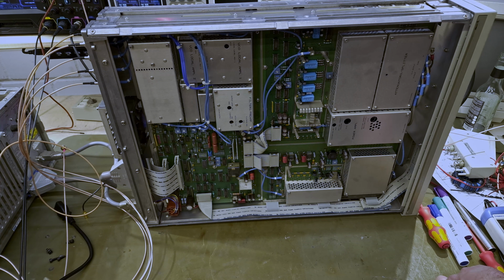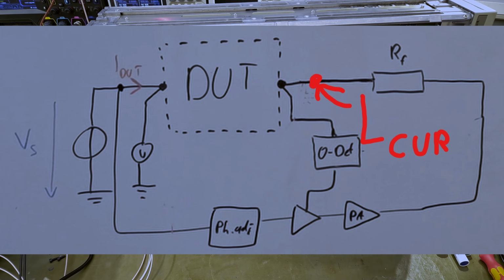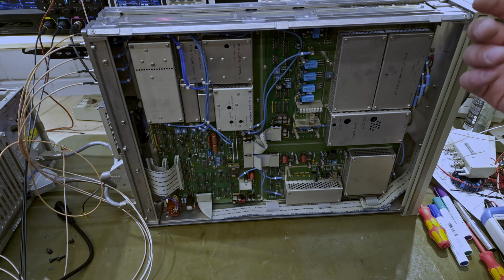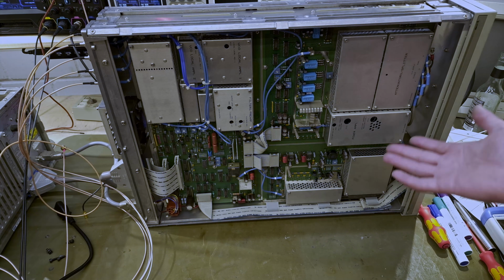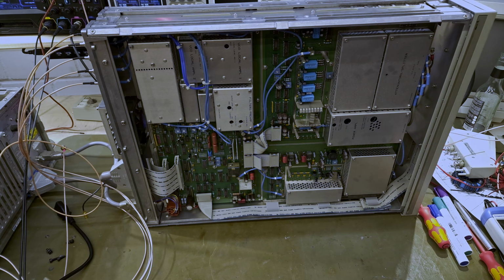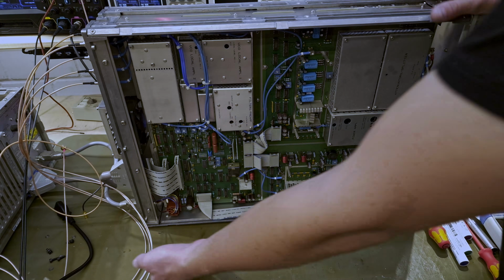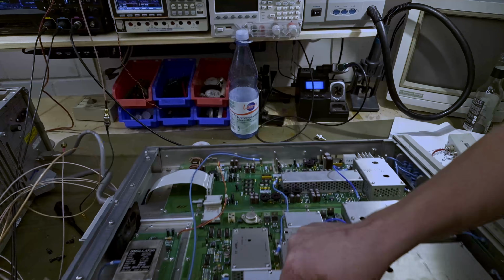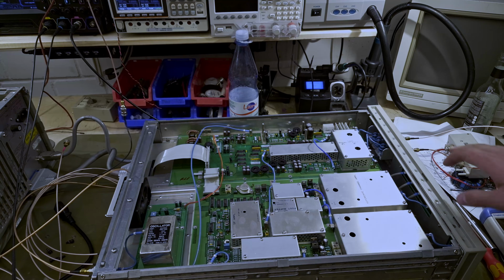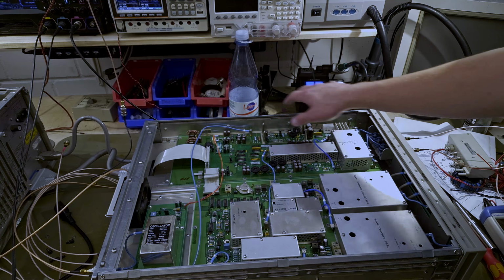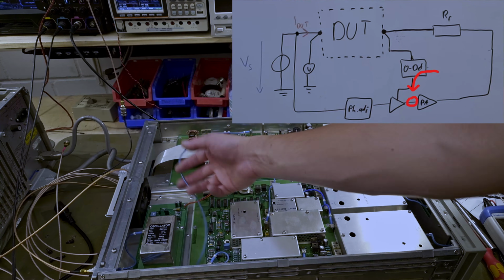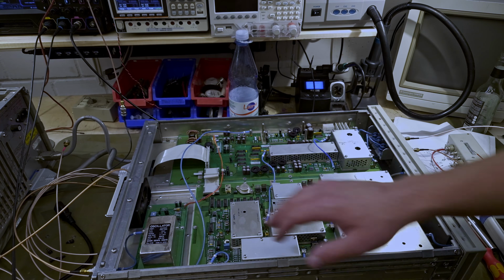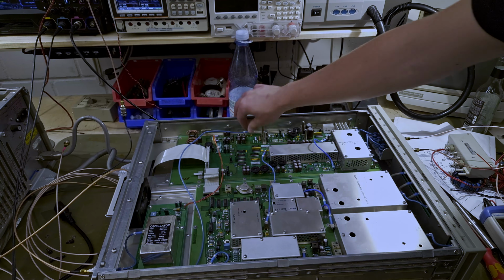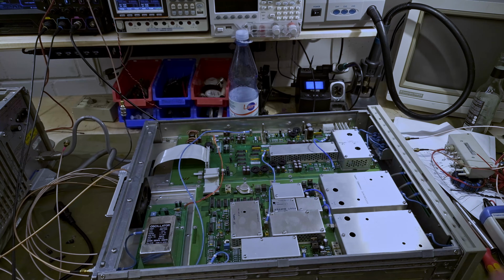Also, at that point, I realized that the low current input actually was at a fixed voltage all the time. And it was a fixed DC voltage, not just some AC signal, which meant there had to be some fault in it. If you just hooked the scope up to it, you had a steady plus 2.8 volts, I believe, on the low current terminal, or L cur. I'm not sure if that's supposed to be low current or whatever, but I'm just going to call it low current. And that sort of made me isolate this section. Again, this is the input signal to the amplifier. This is what you check to be okay when you measure the output of the feedback oscillator on the other board. That goes in here and goes into this section here, which we'll have a closer look at now.